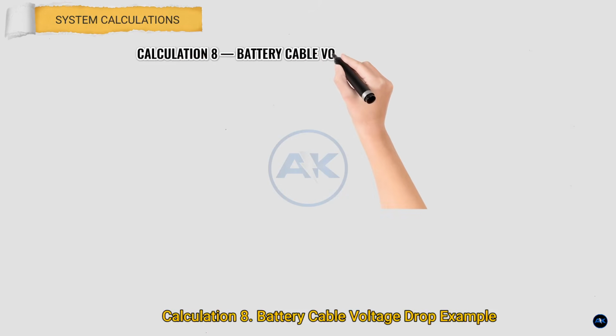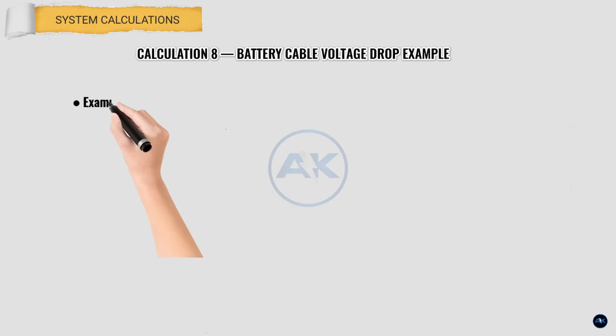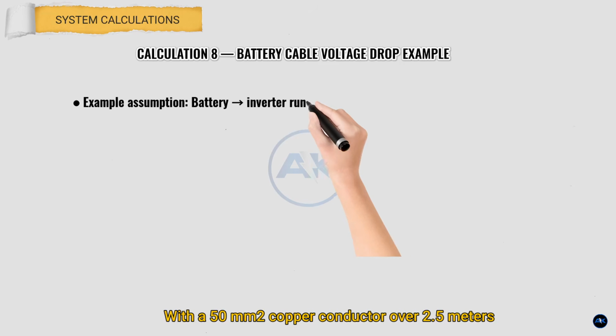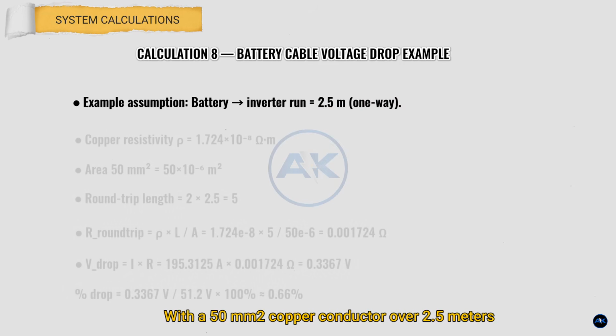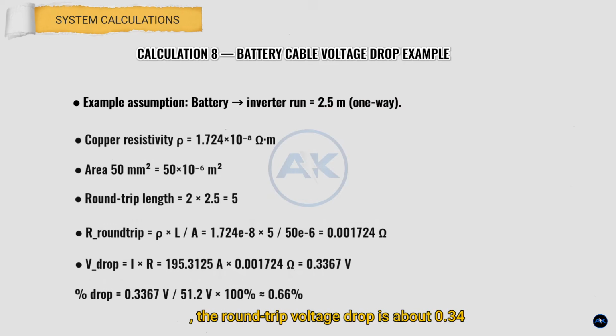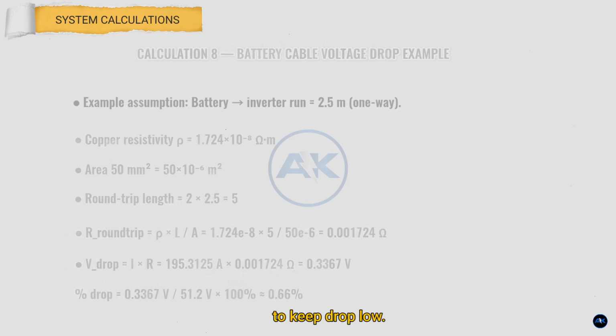Calculation 8. Battery cable voltage drop example. With a 50 millimeter squared copper conductor over 2.5 meters, the round-trip voltage drop is about 0.34 volts, roughly 0.66% of 51.2 volts, which is excellent. If the run is longer, increase conductor size to keep drop low.